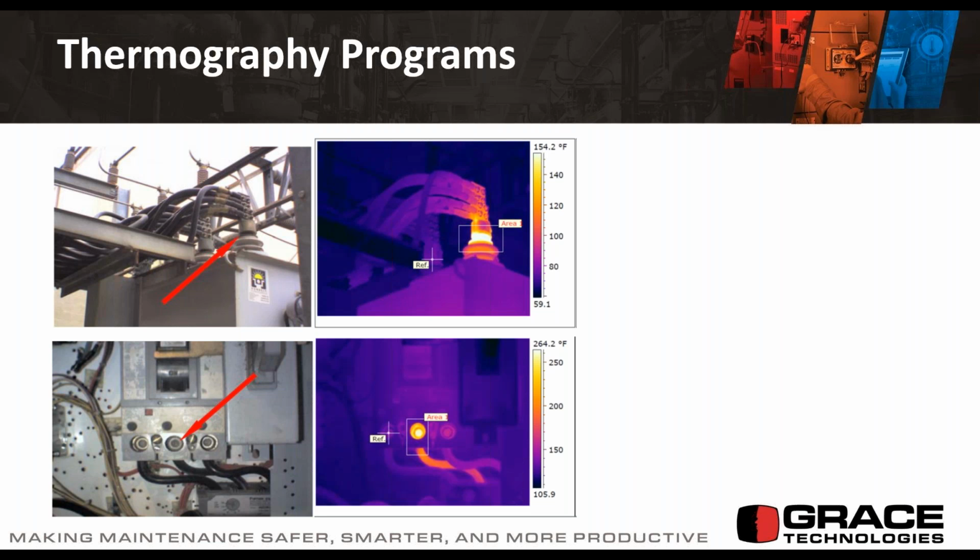And the biggest thing here is, whenever you use a thermography camera, you need to make sure that the system is measured or tested replicating the normal operating condition or normal load. So if the system is designed for 1,000 amps, for example, and the normal loading factor is 85% of it, whenever you're performing this thermography, you need to ensure that it is loaded at 85% capacity to show the actual measurement, because you want a representative sample, not something taken when everything is shut down and someone comes and takes the temperature measurement. That's one of the things we always highlight, because when you call the thermography inspectors or your technicians going around this equipment, make sure that the systems are loaded to the real values, what they're loaded at in normal situations, so it gives an actual value.